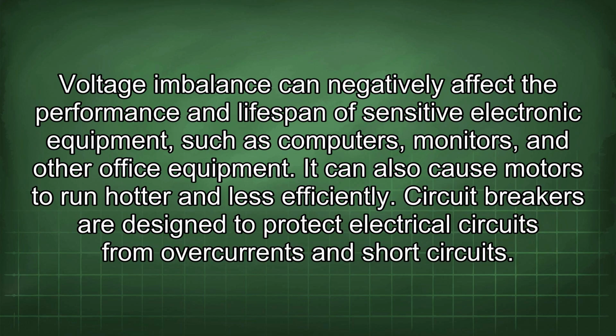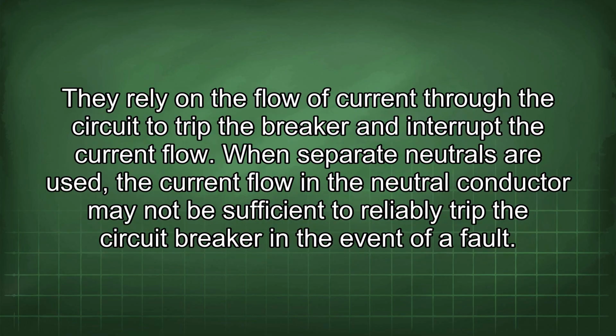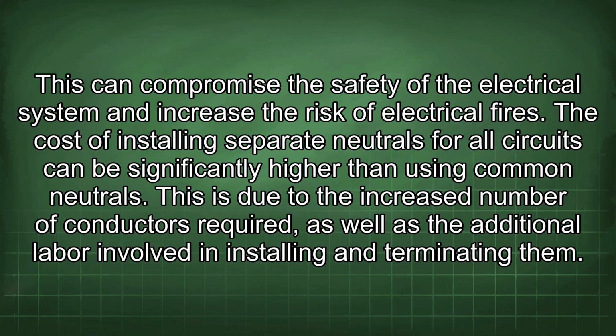Voltage imbalance can negatively affect the performance and lifespan of sensitive electronic equipment, such as computers, monitors, and other office equipment. It can also cause motors to run hotter and less efficiently. Circuit breakers are designed to protect electrical circuits from overcurrents and short circuits. They rely on the flow of current through the circuit to trip the breaker and interrupt the current flow. When separate neutrals are used, the current flow in the neutral conductor may not be sufficient to reliably trip the circuit breaker in the event of a fault. This can compromise the safety of the electrical system and increase the risk of electrical fires.